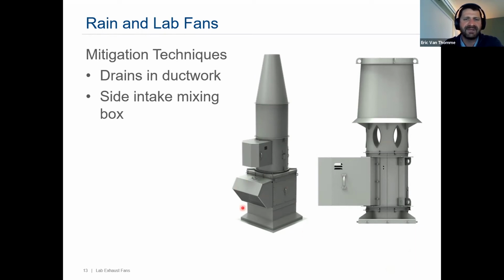Another way is where we have these mixing boxes. So Pennbarry can supply these mixing boxes, which are typically used for common plenum applications. But utilizing a side intake on the mixing box, which really what that requires is a duct penetration through the roof next to the fan, and then an elbow into the mixing box. Then we would put in a solid bottom to the mixing box, and then have a drain coming off of that mixing box as well. So those are really two common methods, and this is a really important aspect to take into consideration when designing a laboratory exhaust fan system.